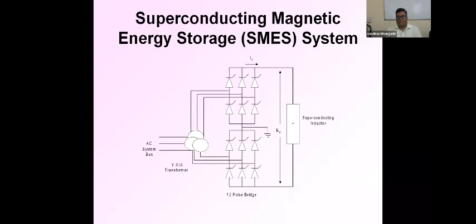When the superconducting coil is charged, it stores energy in the magnetic field. So when there is a load demand in the system, in a control area, the stored energy is released by this inductor coil through the power conversion system to the grid. During the sudden release of load, the coil immediately gets charged to full value. Some portion of excess energy in the system is absorbed by the coil, and as the system returns to steady state, the absorbed energy in the coil is released. This means in the first half cycle it works as a load, and in the second half cycle it works as a source.